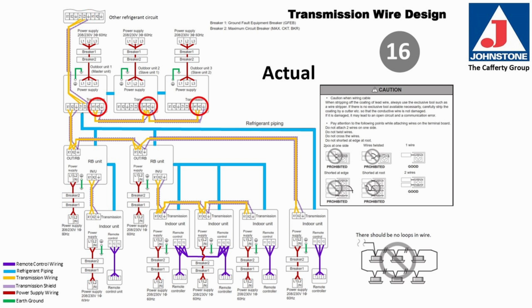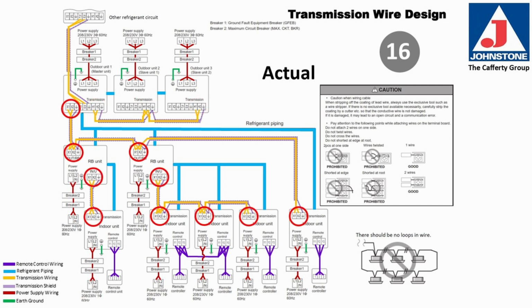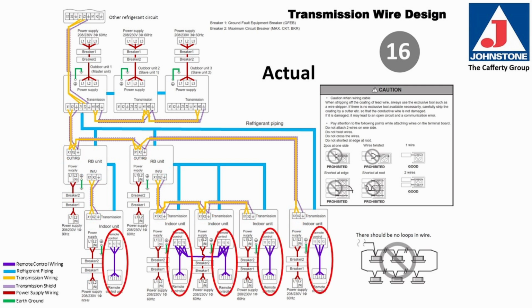Here are the connections between all of the outdoor units on this refrigerant circuit. Here are the connections on the circuit between the outdoor unit, the RB boxes, and the indoor units. Here are the connections for the remote controllers. You'll notice here that two of the indoor units are connected together. That means that they are both in the same space. This could be a larger room where we could have a controller at each end of the room, and in this case, those two controllers would mirror each other. When you change the settings on one, the display would change on the other.